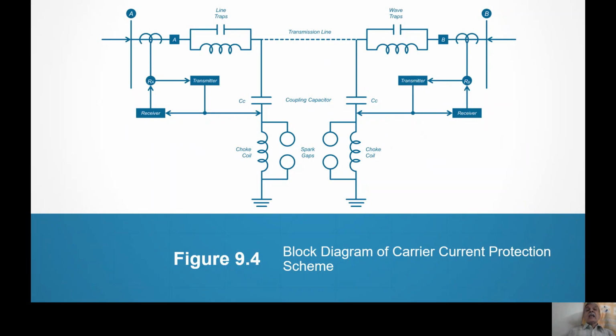There is a line AB, which is obviously fed from both ends, because when we are using carrier current or distance protection, we are taking it for granted that we are working in an interconnected system. So it is fed from both ends. But usually the power would be flowing either from A to B or B to A. But when a fault occurs, power will be fed from both ends. So here that fault condition is shown.